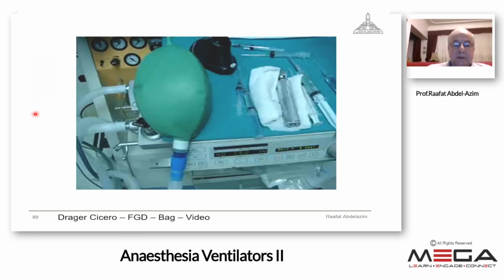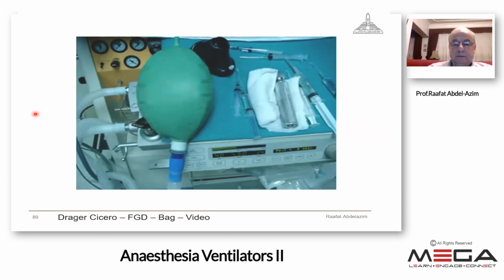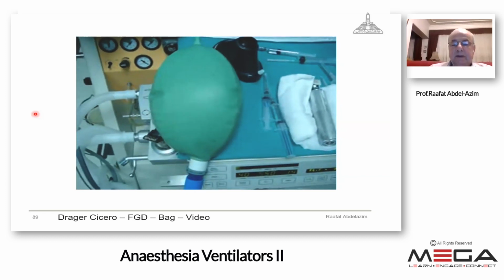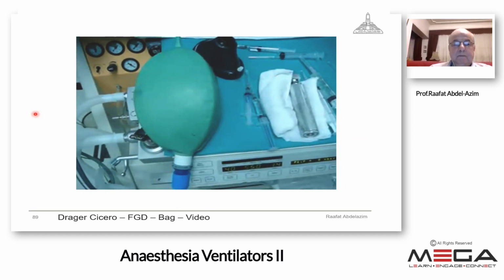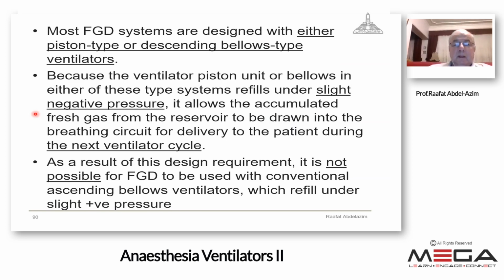Now we see in this video, in the Cicero anesthesia ventilator Drager, that the fresh gas will move into the reservoir bag, inflating it during inspiration. At the same time, the patient's lungs are inflated. For activating the fresh gas decoupling system, the manufacturer has designed the ventilator to have either the piston type that I described before, or descending bellows, that we stop using in the traditional ventilator.